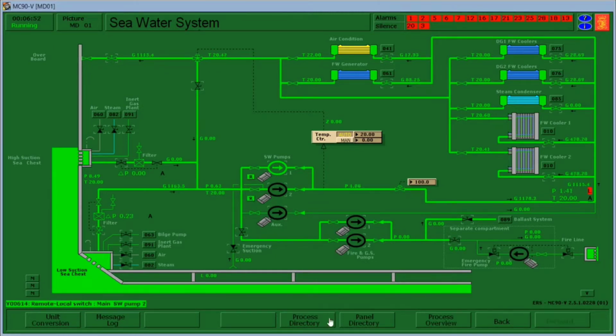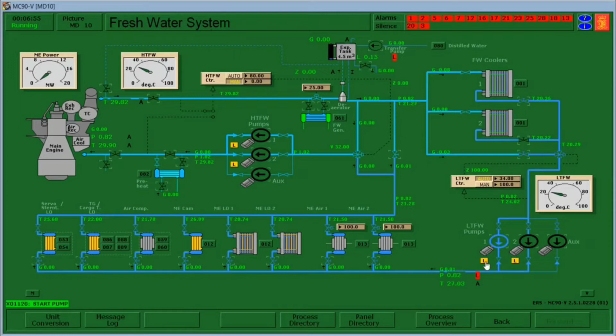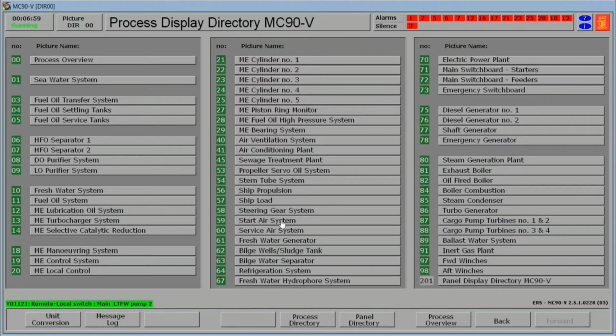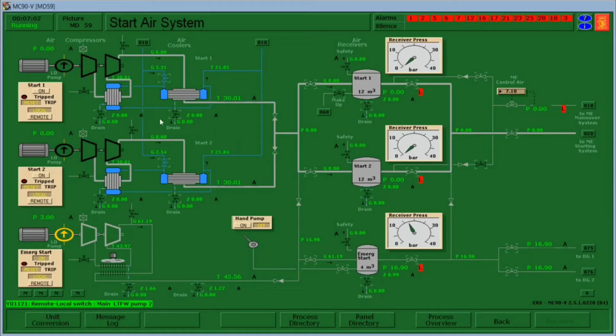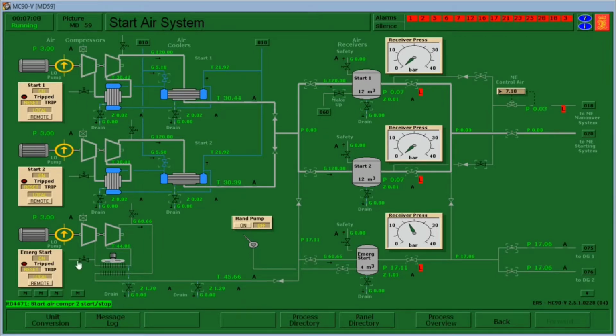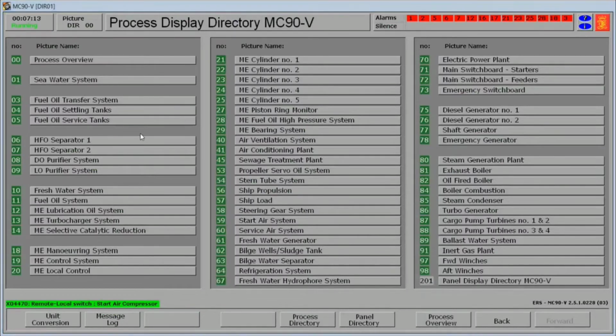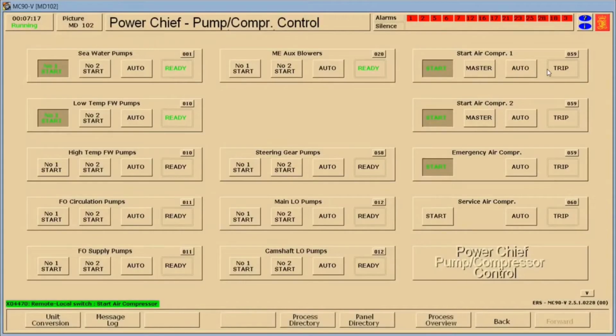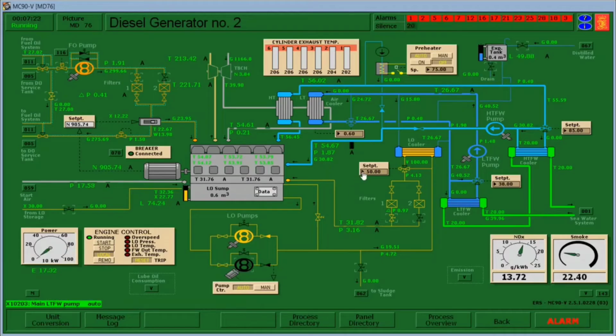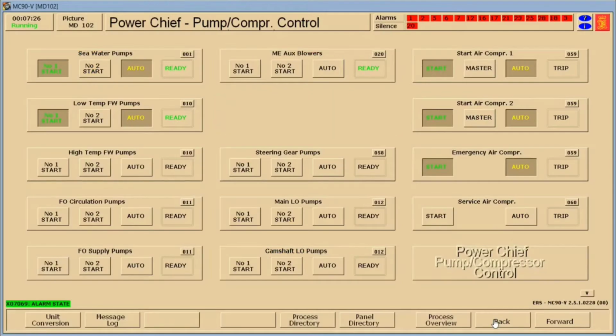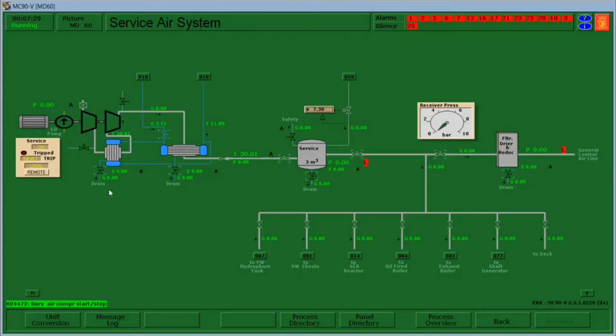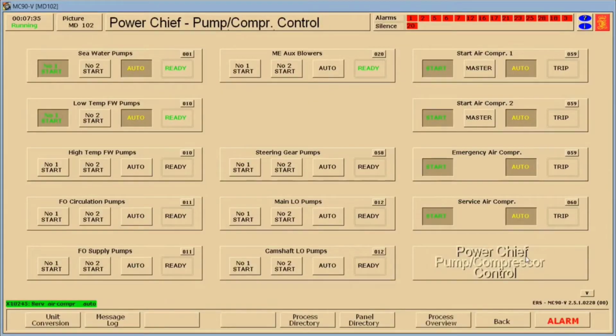Set local to remote. Proceed to freshwater system, set local to remote. Then proceed to start air system, start the air compressors, set to remote. Proceed to panel directory, Power Chief pump controls, air compressor 1, seawater. Then acknowledge the alarm. Then proceed to service air compressor, press on, set to remote, and auto.